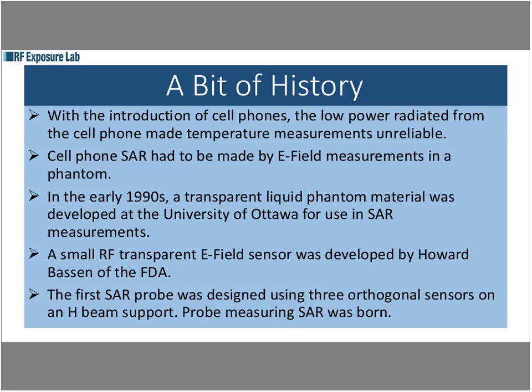Obviously today we don't have that. We have the SAM phantoms that are all simulated devices for test purposes. The small RF transparent E-field sensor was actually developed by Howard Bassen of the FDA. That's really the first design that came out with the orthogonal sensors, which is still basically used today in all of the SAR probes, where we use 3 orthogonal sensors on an H-beam support. And that probe basically set the framework to start measuring SAR at that point.